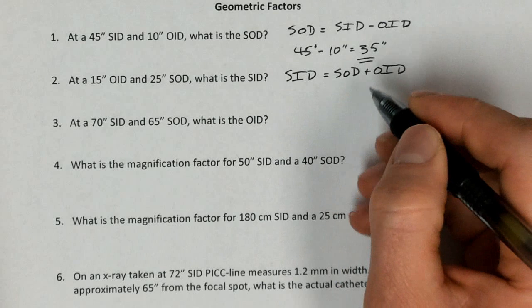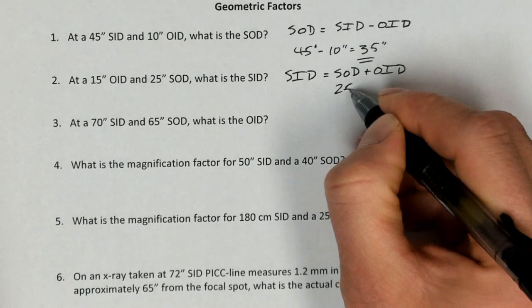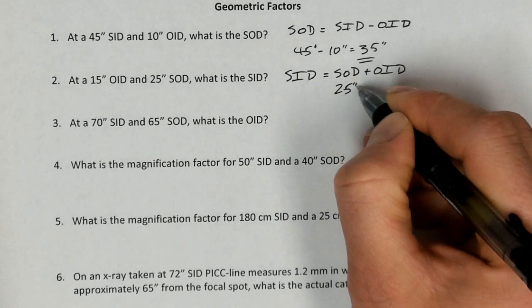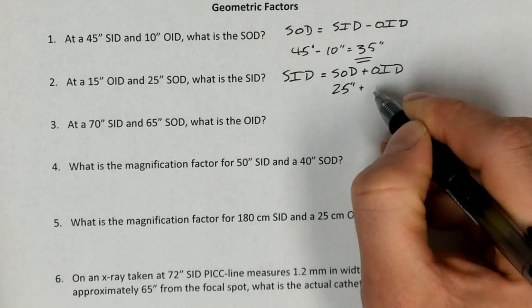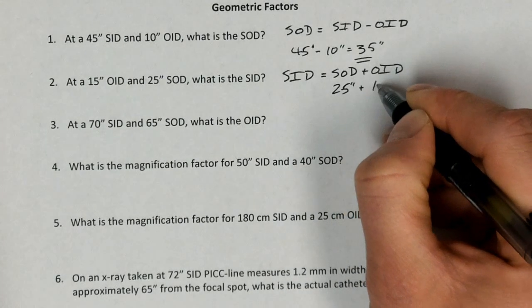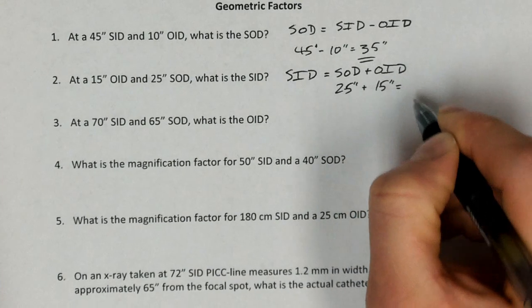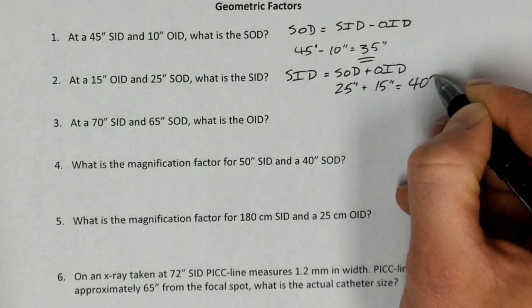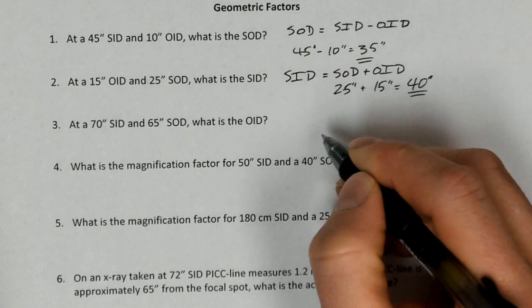So in this case, the source to object distance is 25 inches. The OID is 15 inches. And so when we add those together, we get 40 inches. This is a 40-inch SID, a very common SID.